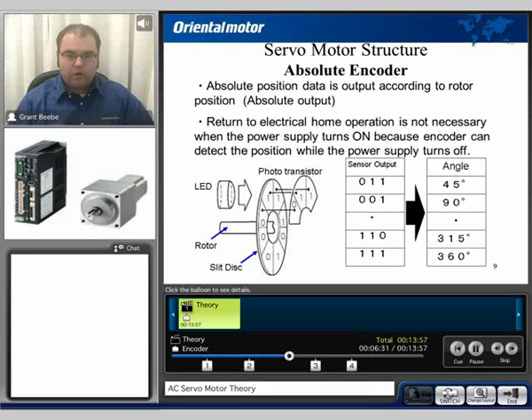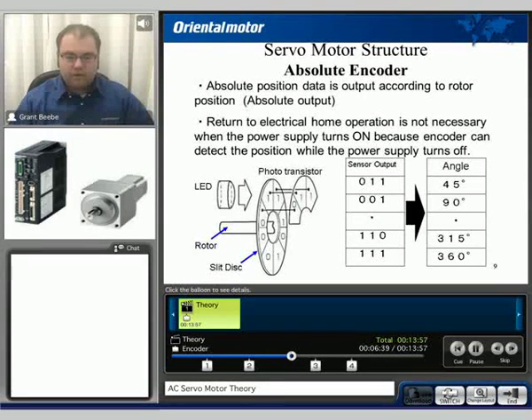For example, at 45 degrees the sensor output may look like a specific binary pattern; at 90 degrees it might look different, and so on. Return to mechanical home is not necessary with an absolute encoder when moving between zero and 360 degrees, simply because that specific angle on the encoder is kept track of on the encoder itself and not in volatile memory in the driver.